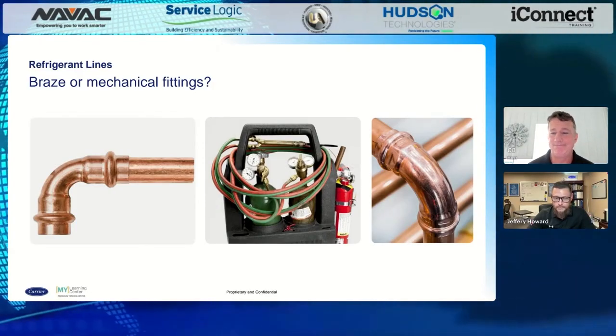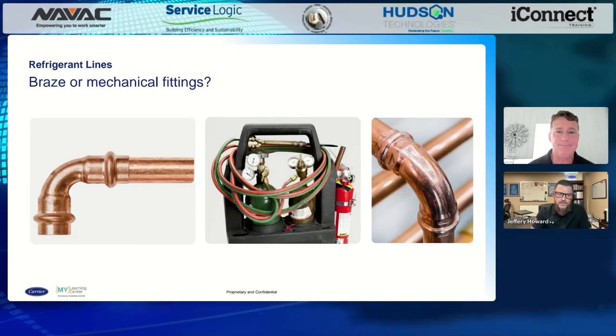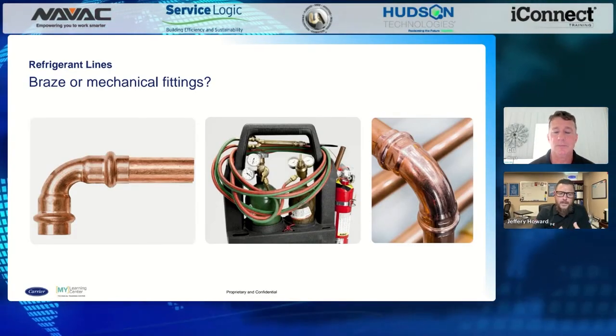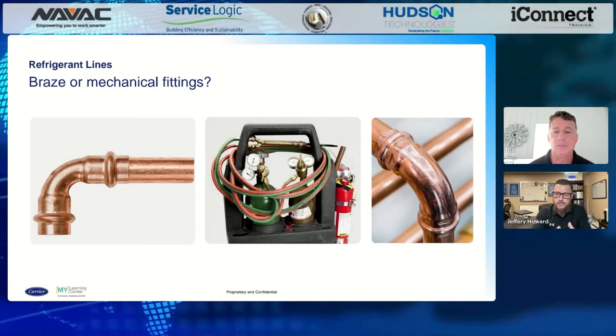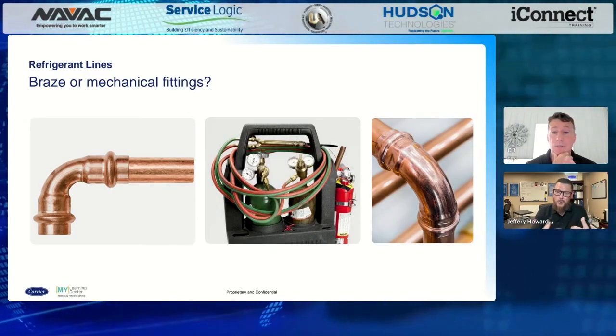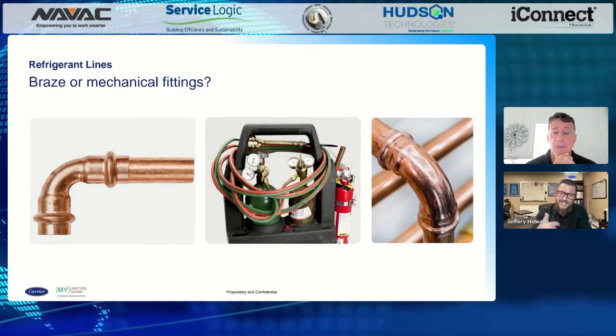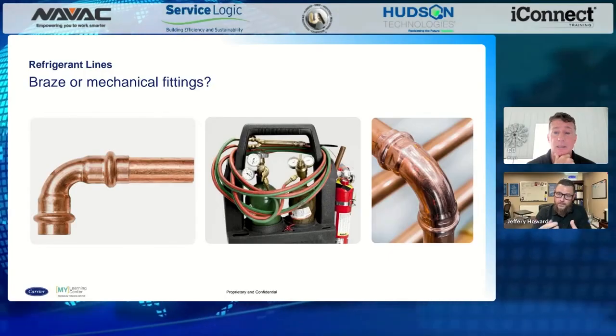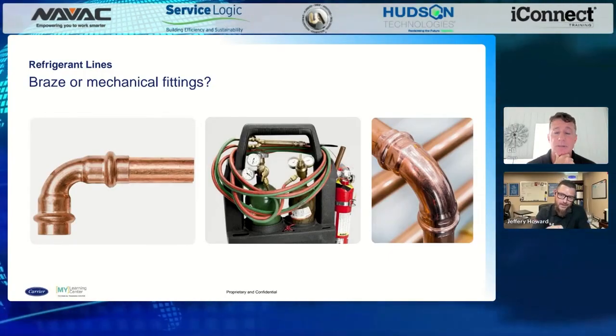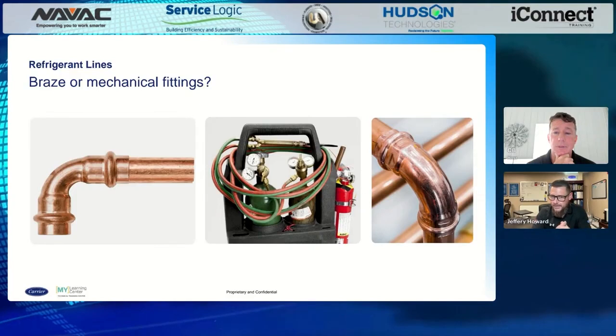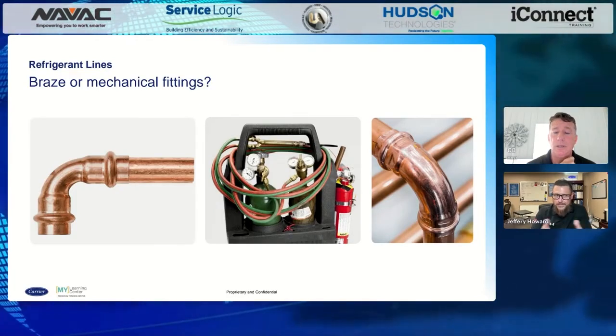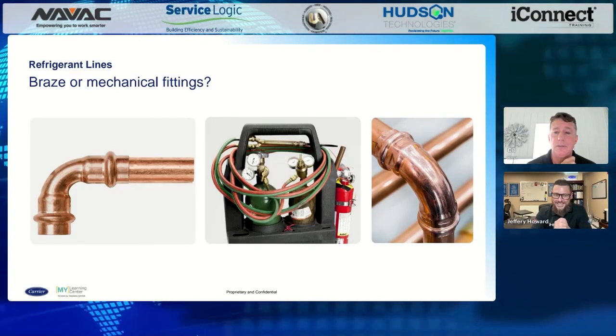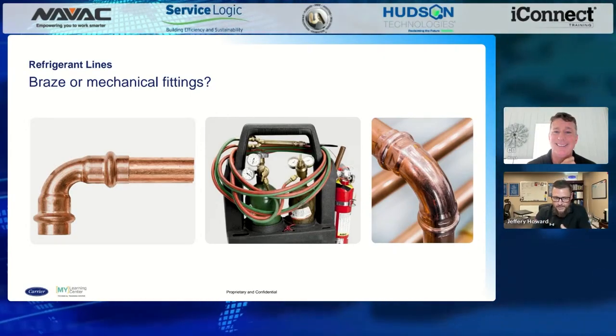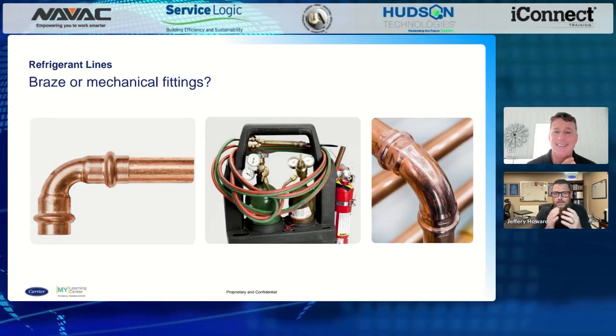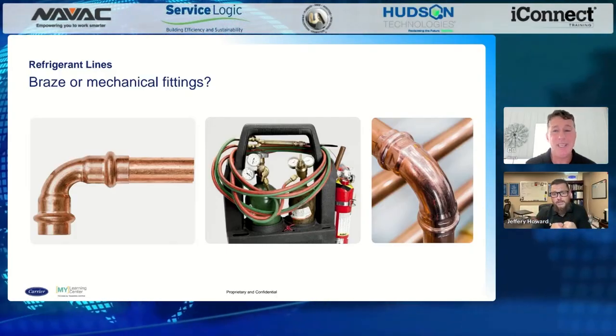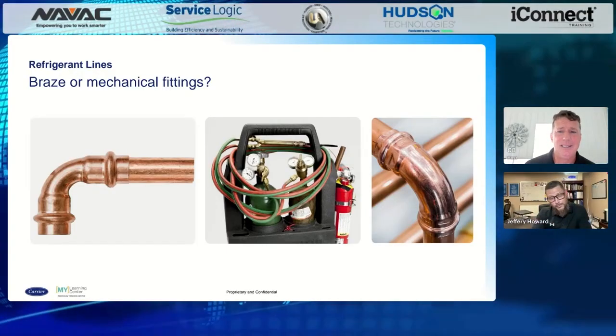So much so, on our equipment we went ahead and changed our outdoor units to straight stub-outs, because what we were seeing in the field was technicians becoming more comfortable with mechanical fittings and cutting the bell. When you cut the bell reducer, it's too close to the valve body and you can't really get your tools in there for those fittings. So they were having issues using mechanical fittings in that regard. With the transition to our Puron Advance, we said let's help—how can we help, what can we do to make it easier for the field?